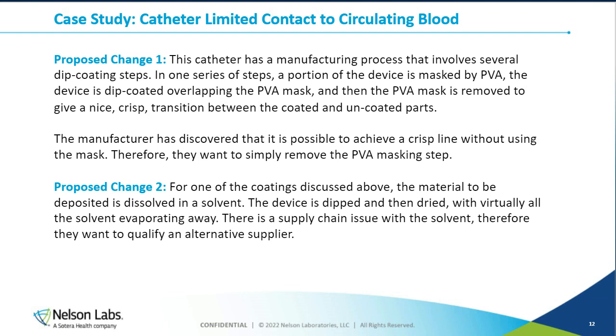And we'll often look at that and say, okay, how long does the device contact the liner? And how much time is really needed to have effective transfer of something from something like an FEP liner to a catheter? And more often than not, there's some sort of evidence or supporting information that the manufacturing fixture or the liner is clean, right? So if the liner's clean, that means there's some evidence that there are not residual materials on the surface of that. And if the fixture is clean and it contacts the device, then there's really very little chance for transfer of unwanted chemicals or materials from the liner to the catheter. And so what we would generally do is go through and explain that using some supporting information, like evidence that this thing is clean.